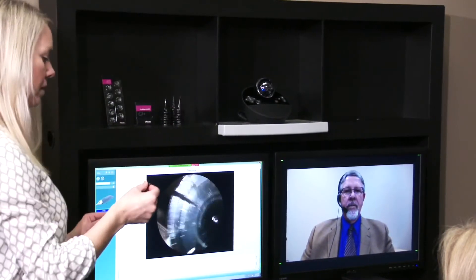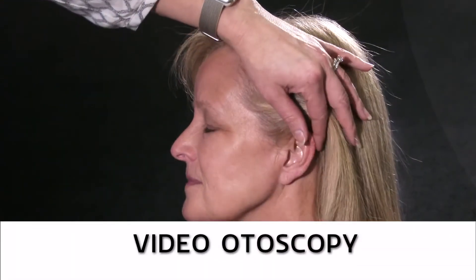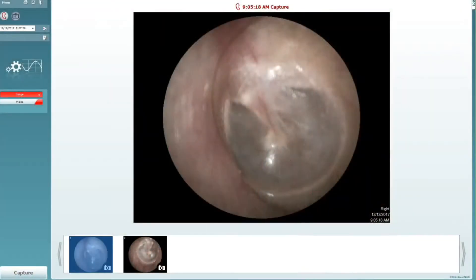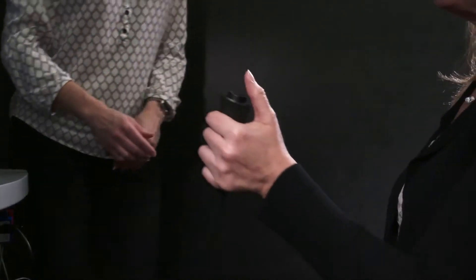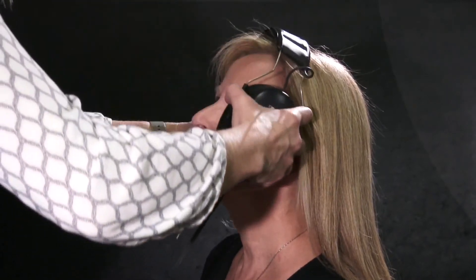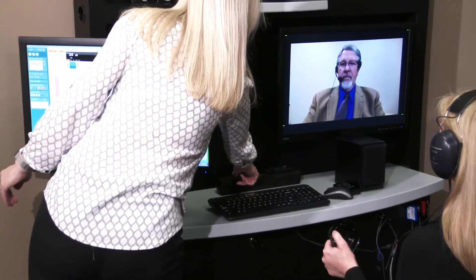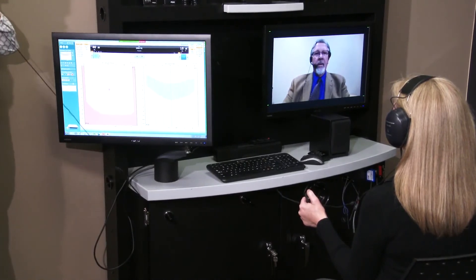Depending on the examiner's and technician's protocol, one of them will explain the test procedure. The technician typically performs video otoscopy as the first step. The patient remains engaged by having the full view of the video image on the test screen. The examiner explains the pure-tone test process, and the technician provides them with the patient response switch and places on their headset. The technician repositions the audiometric test screen so the patient cannot view the audiometric test in progress, then mutes the speaker system, and the examiner begins the pure-tone air conduction audiometric test.